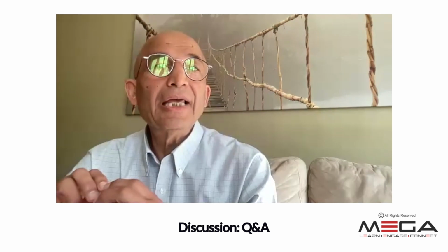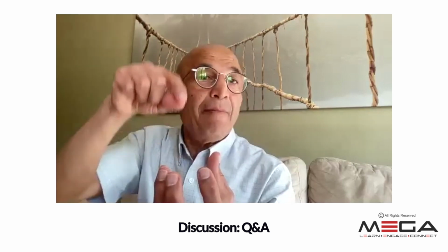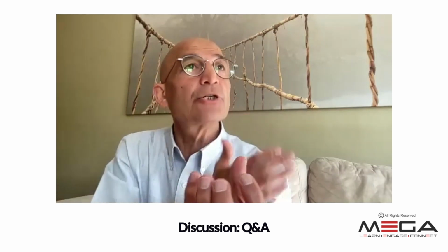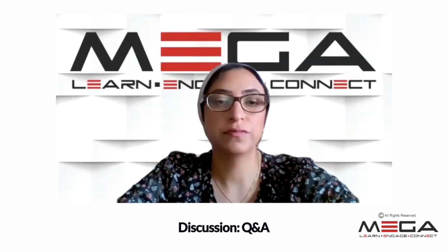However, they described a different switch for the pacemaker called the Hall effect sensor. With the Hall effect sensor, they got the pacemaker and then applied the magnet over the pacemaker. But instead of having a magnet inside the pacemaker like a reed switch, they put some sort of circuits that react to the magnet and interrupt the circuit and unleash the asynchronous mode. So with a reed switch it is magnet over magnet, and you cannot take the magnet out of the pacemaker because it is implantable. But with magnet over electricity, you can reprogram the pacemaker before going into the MRI.